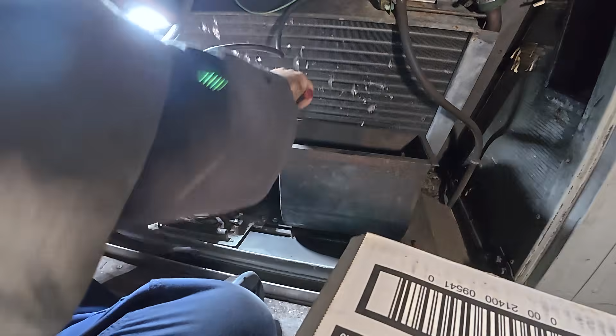Remember, this motor's junk, but if you needed to, this motor's got to have a rebuild - the stator's messed up in it. So it's pulling more amperage than the circuit allows, and that's causing the breaker to trip.